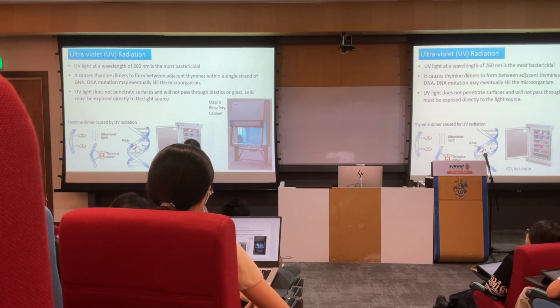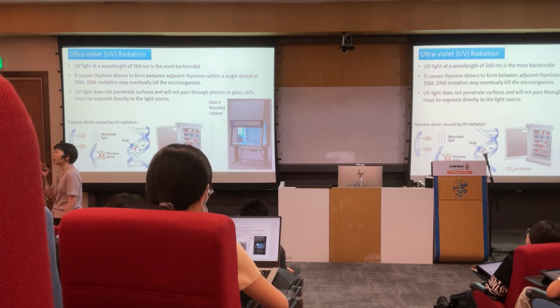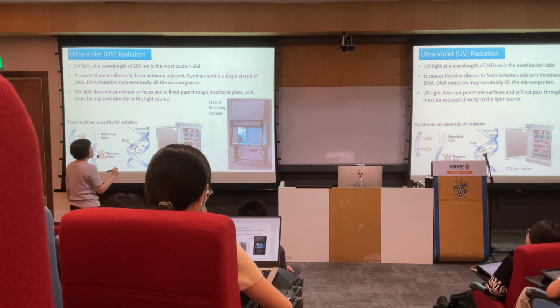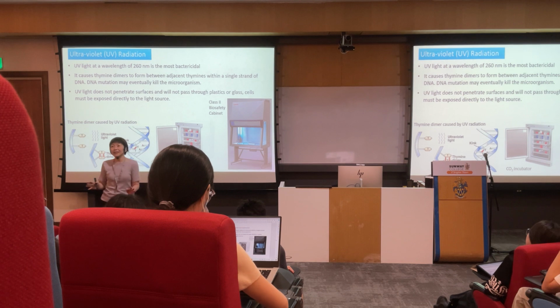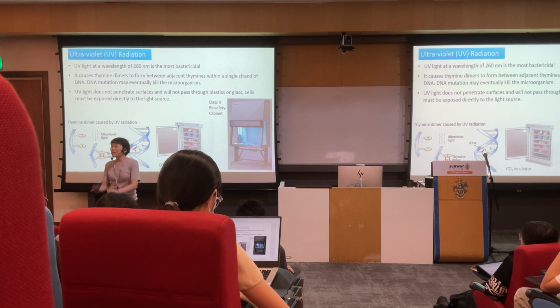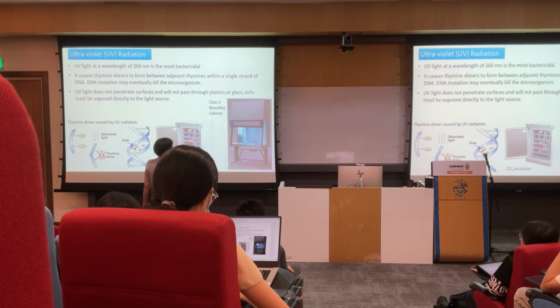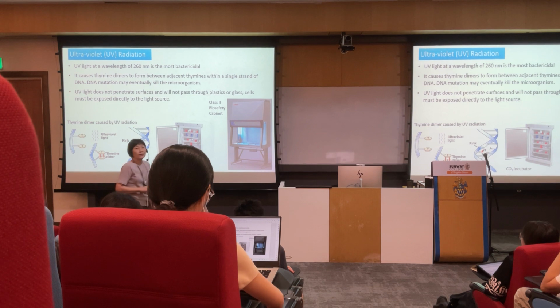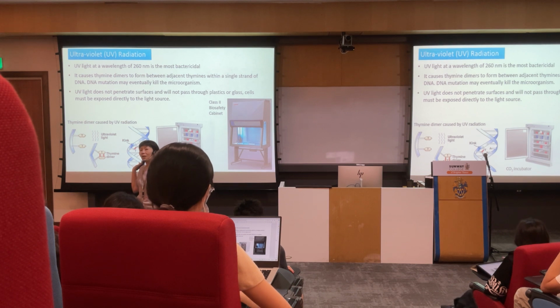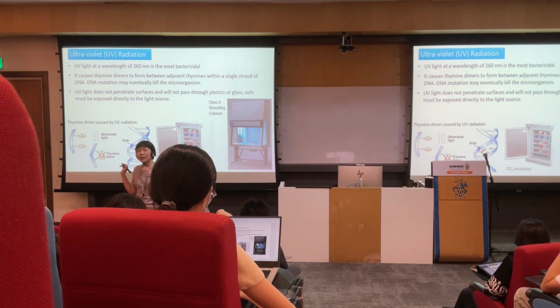UV light is normally applied in the biosafety cabinet. I'm sure you have seen this, every single lab has a biosafety cabinet. Before you use the biosafety cabinet, there is normally a procedure. Because you want it clean, you turn on the UV light for 10 to 15 minutes, just to make sure that everything inside is killed, because it can kill effectively. And the CO2 incubator, normally we keep it to culture human cell lines. So it doesn't turn on all the time, because we always use the incubator, but we need to clean the CO2 incubator from time to time. When we clean it routinely, we turn on the UV light.